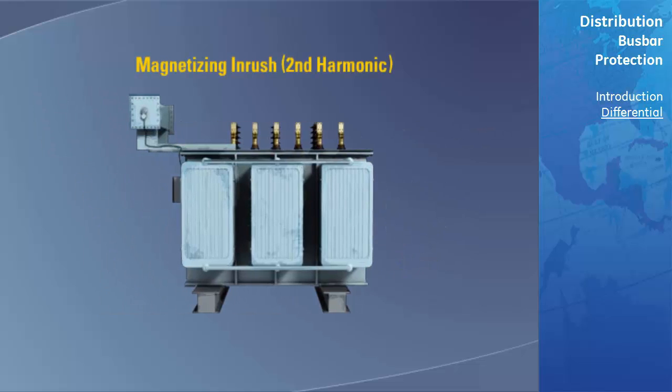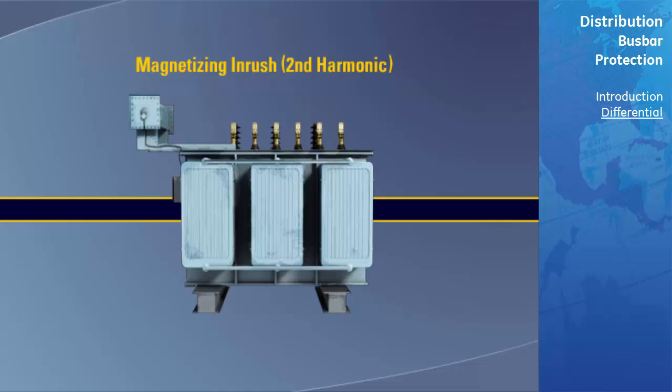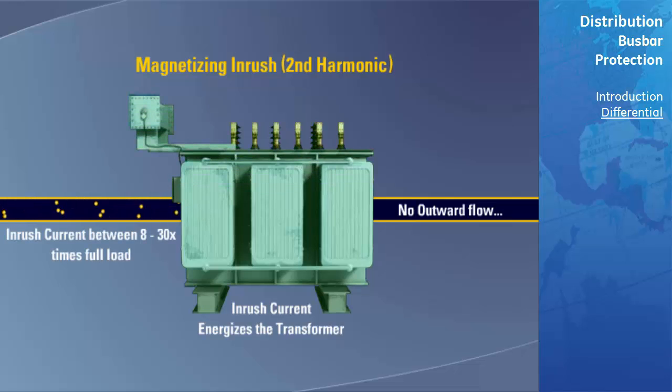Magnetizing inrush or second harmonic. This is a normal characteristic of a transformer that is being energized. When the system voltage is applied to a transformer at a time when the steady-state flux should be at a different level from that existing in the transformer, a current transient, known as inrush, occurs to build up the flux. Inrush currents between 8 to 30 times the full load current flow into the transformer with no current flow out. This current flow would normally appear as an internal transformer fault to the differential element.